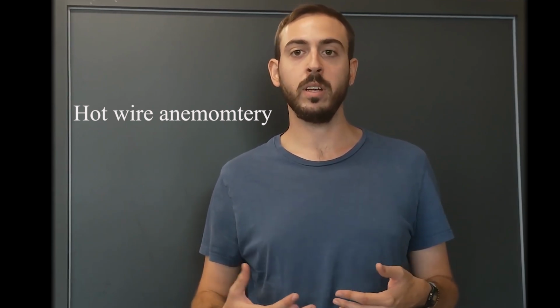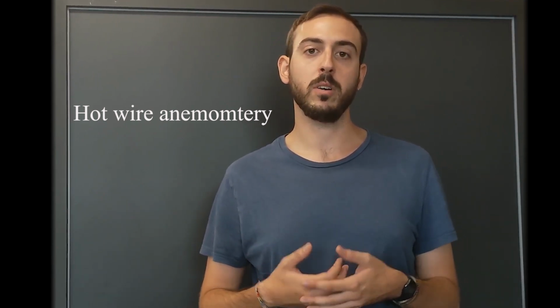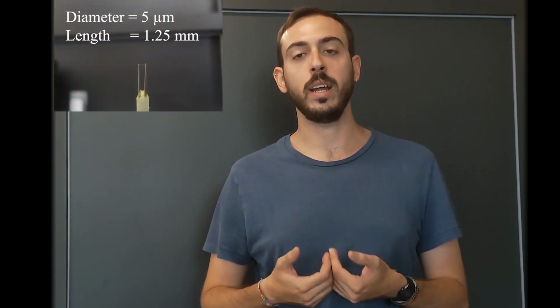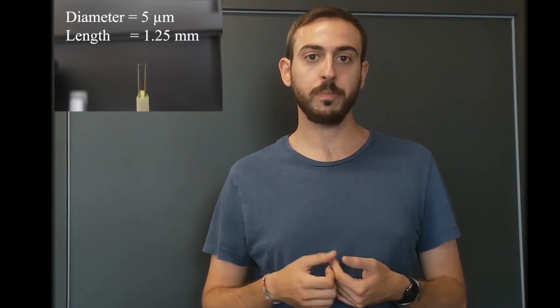Hot wire anemometry is an experimental technique used for the measurement of velocity in turbulent flows. This technique relies on the variation in heat transfer from a small heated sensor exposed to the flow. In this case, the sensor is a small tungsten wire with a diameter of 5 microns and a length of 1.25 millimeters. These sensors are usually manufactured with materials whose electric resistance changes significantly with temperature, such as tungsten or platinum, since this phenomenon will allow us to generate a measurable signal.